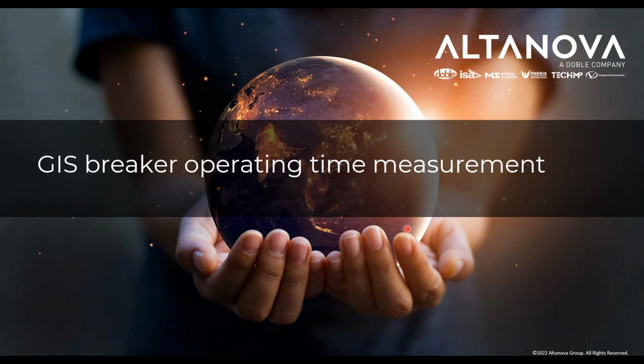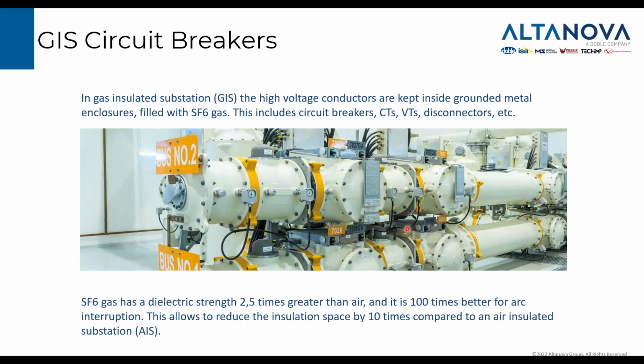A special attention must be paid to GIS breakers because the main contact is inside a metallic enclosure. You cannot easily get access to what is inside, and you would like not to touch anything in the breaker. You don't want to unscrew bars or any part only because you have to make a test on this breaker.